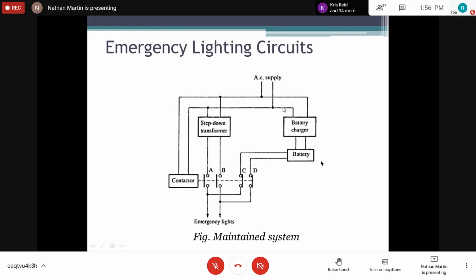However, if this has no supply here, right, meaning this step-down transformer will not be energized, then this will open and then this contact will be closed. In the other situation where this is energized, these will be closed, right, and this will be closed. So in this one, at all times, there is power reaching the emergency light.